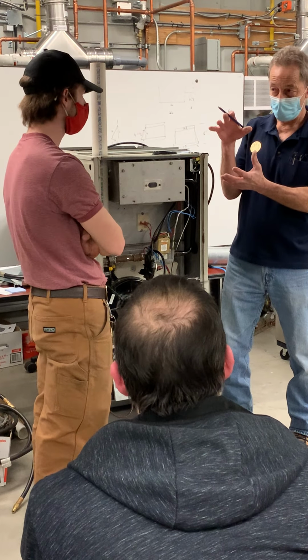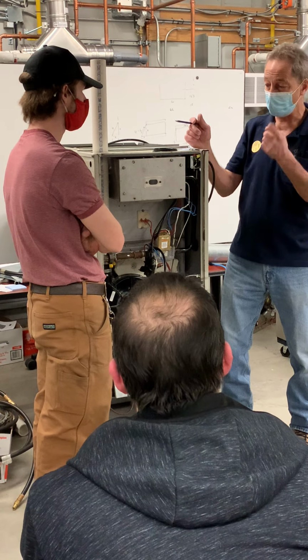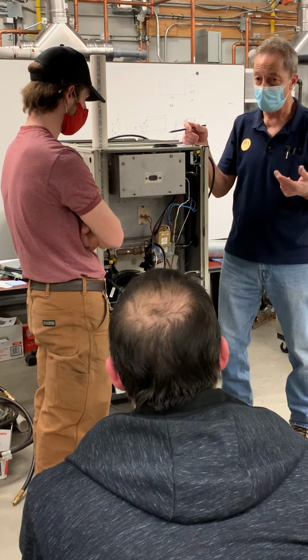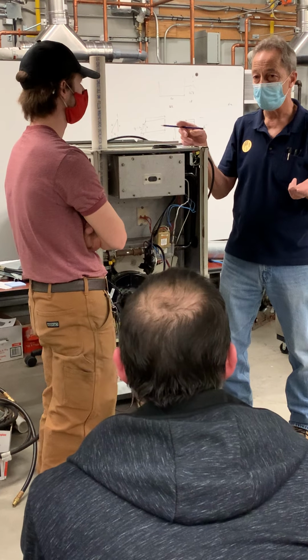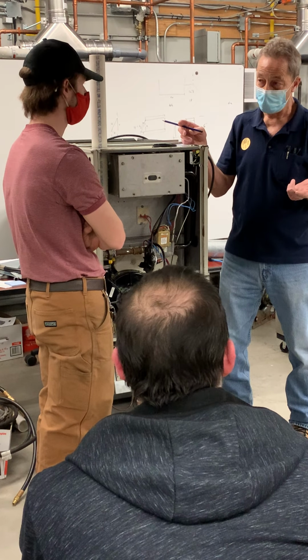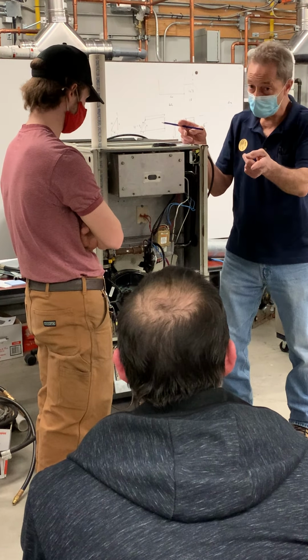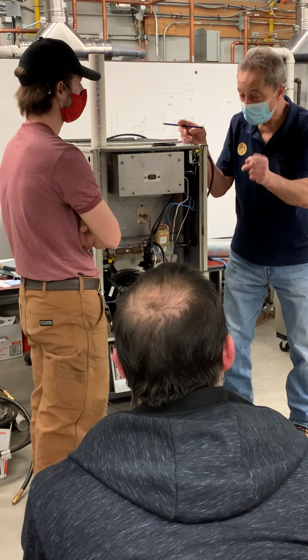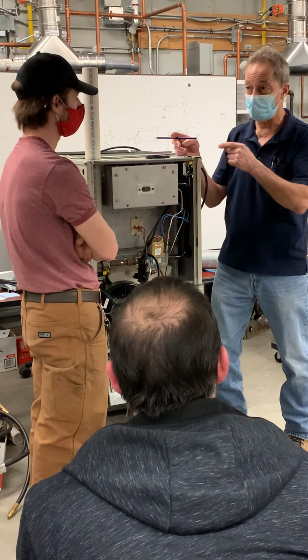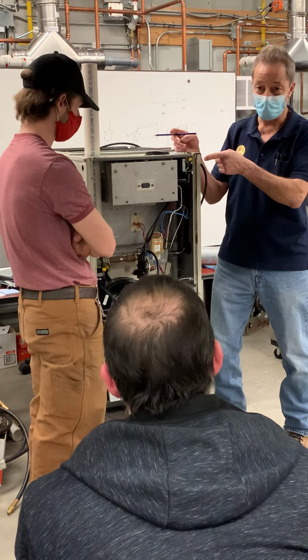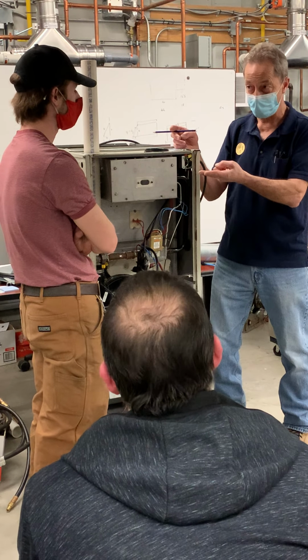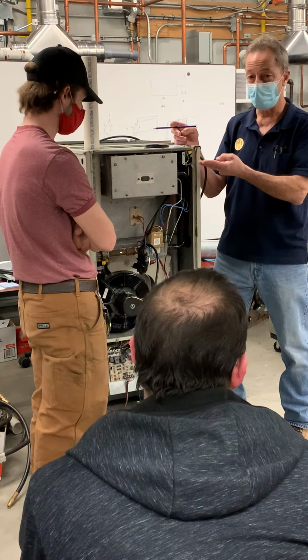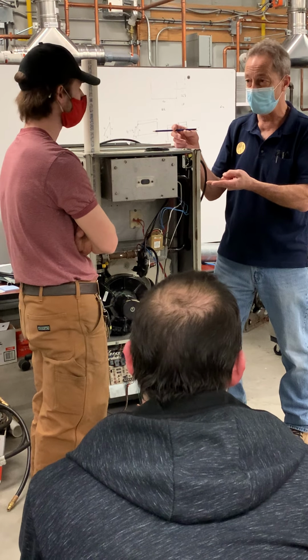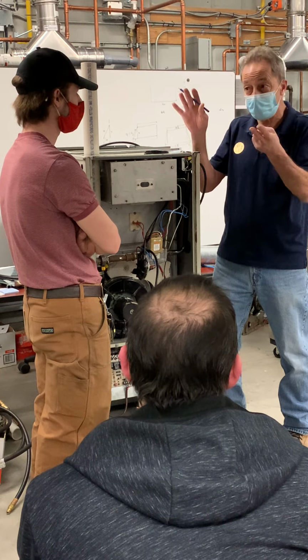It self-checks. Thank you, self-check. So what do I have to do to make it, or encourage it to self-check? What do you have to do? Um, that's what needs to be energized. Exactly, you gotta give it how many volts? 24. So you give the gas valve 24 volts. Now you can do the self-check. You can't do a self-check if you don't have voltage, right? Right. So it does the self-check, everything says good.